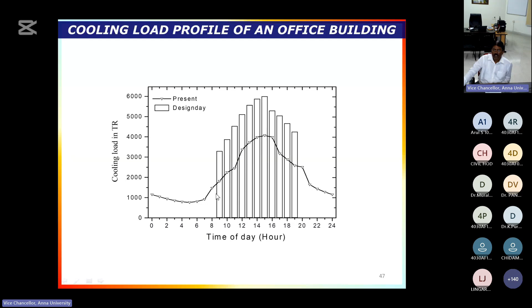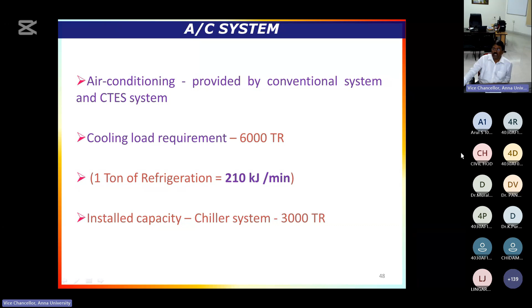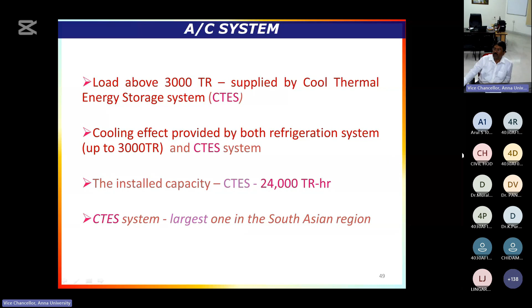Because of this, even though their requirement was 6,000 TR, they installed only 3,000 TR with a full storage capacity of 24,000 ton-hours. Kilowatt means power, kilowatt-hour means energy; similarly, ton means air conditioning capacity, and ton-hour means energy utilized by the system. So 24,000 ton-hours stored means if you use 1,000 tons, the storage tank will deliver for 24 hours.